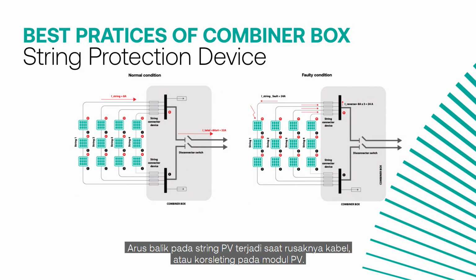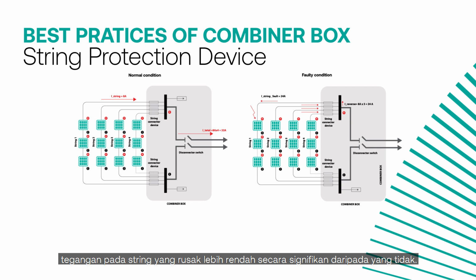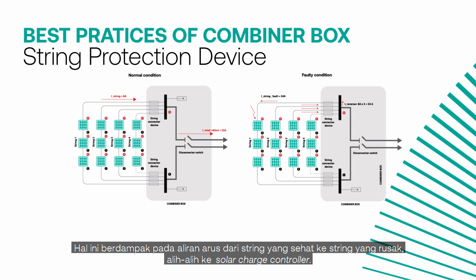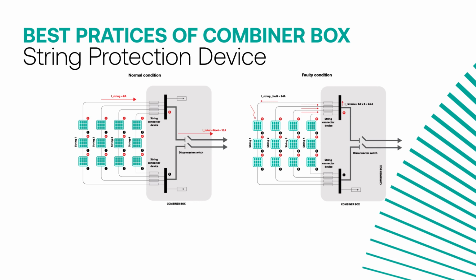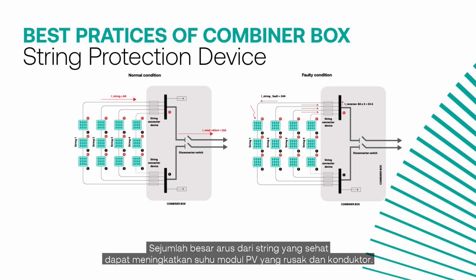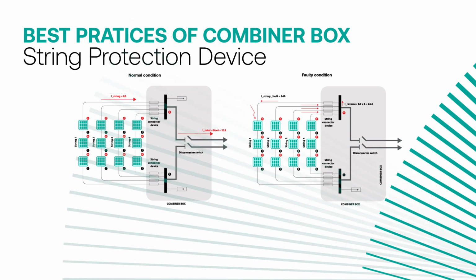The reverse current in PV strings occurs in the event of faulty wiring or a short circuit in a PV module. During normal conditions, the current of each string is summed and fed into the charge controller. Once an electrical fault occurs, the voltage of the faulty string is significantly lower than the healthy ones. This results in a flow of current from the healthy strings to the faulty one instead of the solar charge controller. A considerable sum of current from the healthy strings may increase the temperature of the faulty PV module as well as the conductor. It also possibly causes fire if no overcurrent protection is installed.